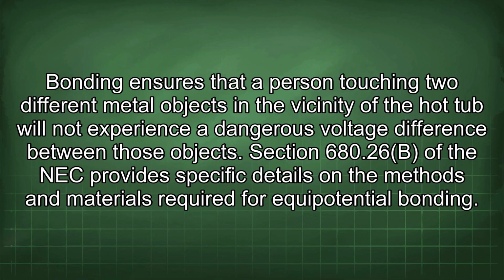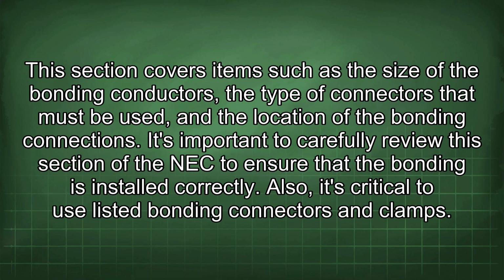Section 680.26(B) of the NEC provides specific details on the methods and materials required for equipotential bonding. This section covers items such as the size of the bonding conductors, the type of connectors that must be used, and the location of the bonding connections. It's important to carefully review this section of the NEC to ensure that the bonding is installed correctly.